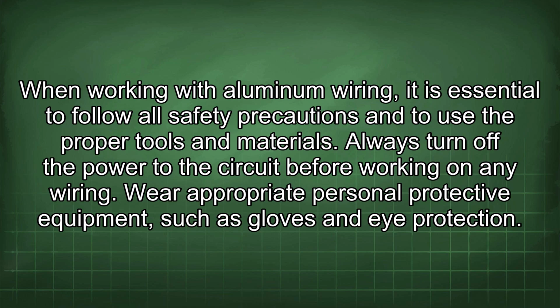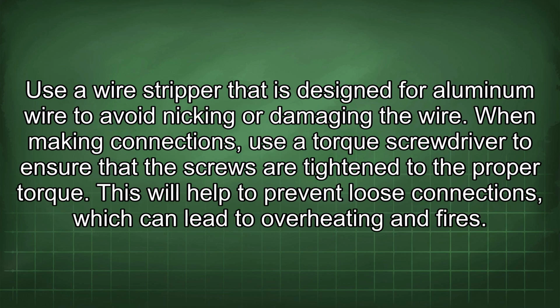When working with aluminum wiring, it is essential to follow all safety precautions and to use the proper tools and materials. Always turn off the power to the circuit before working on any wiring. Wear appropriate personal protective equipment such as gloves and eye protection. Use a wire stripper that is designed for aluminum wire to avoid nicking or damaging the wire. When making connections, use a torque screwdriver to ensure that the screws are tightened to the proper torque. This will help to prevent loose connections, which can lead to overheating and fires.